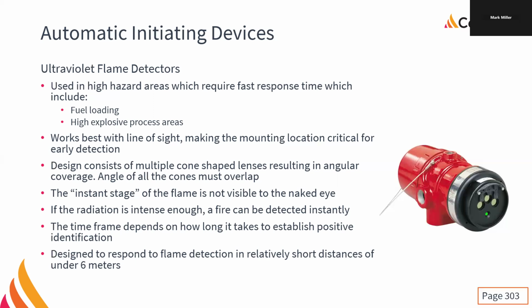The actual detection of the flame, if it's a large enough fire, it gets detected, while not instantly, as close to instantly as you can get. So if you take a garbage can and light it on fire, the inside of a garbage can, that big of a fire will be detected effectively instantly at 200 feet away. Very, very responsive. Of course, the larger the fire, the faster it's going to respond. The closer it is, the faster it's going to respond because in its viewing angle, it's just going to take up more space. So there can be some delays, but it is still pretty quick.